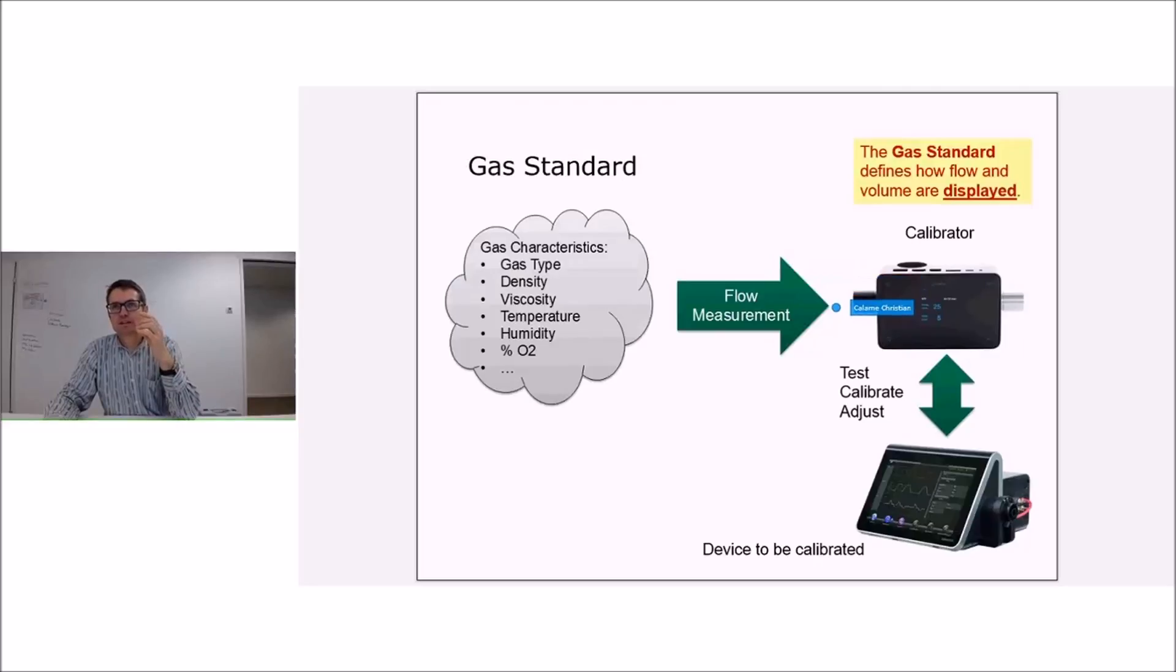However, those standard conditions unfortunately have not become a standard for displaying, and then the whole measurements are recalculated and then displayed in a certain world or in a certain standard, which is the gas standard. So that's something people very often confuse. They say, okay, we want to measure proximal to the patient, so we have to take a gas standard which includes humidity. It's not. You just have to take that into account when you measure, and how you display is yet another topic. So that's something which creates a lot of confusion, the gas standard.